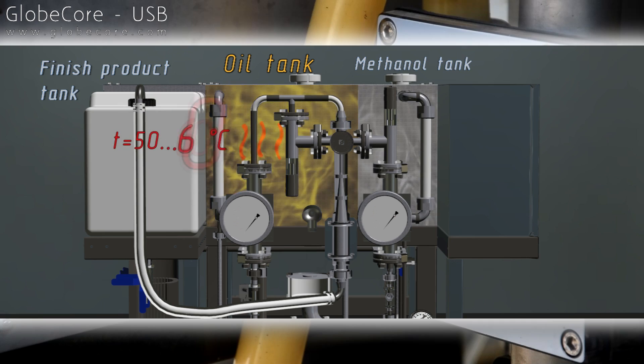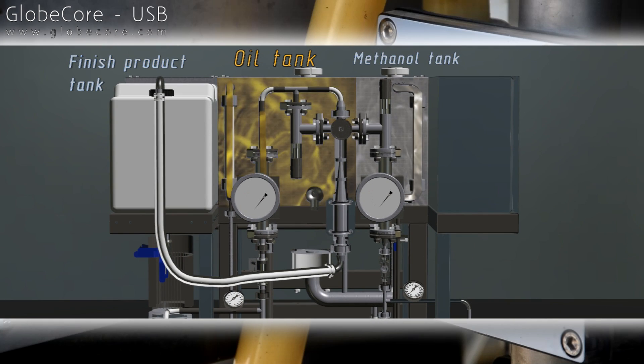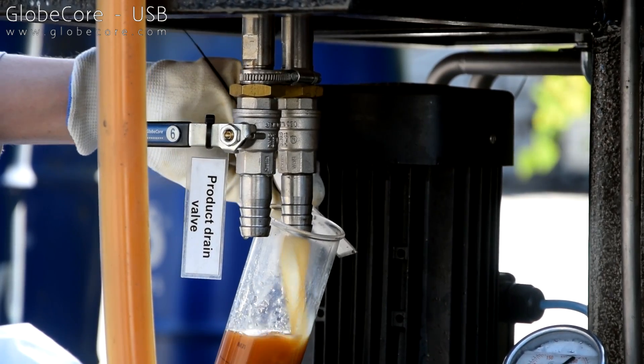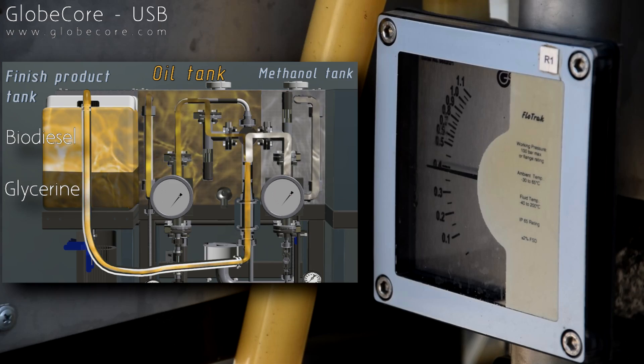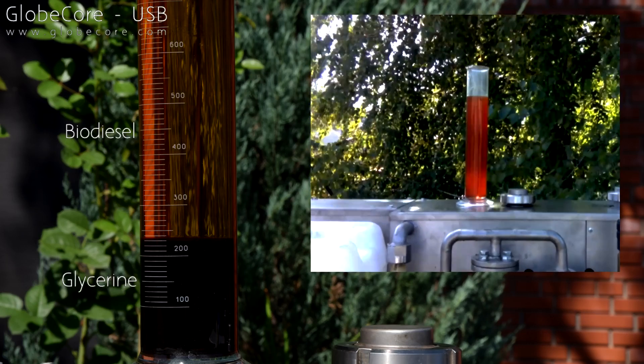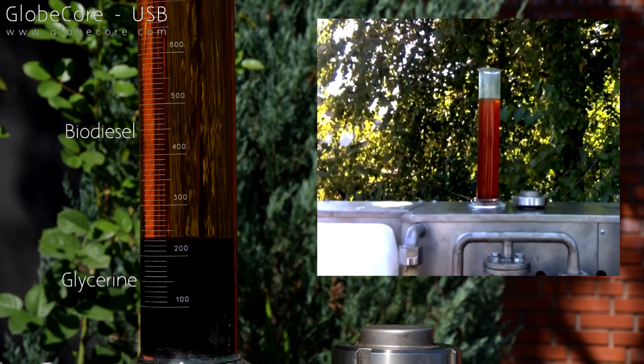The system is designed for specialized biodiesel production facilities, as well as for oil refineries, food processing facilities or farms. The operation principle, as exemplified by a demonstrator unit, is to prepare the components and create the conditions required for transesterification. One vessel is filled with vegetable oil – in our case, waste frying oil. The other vessel is filled with a solution of catalyst in methanol. Oil temperature is set to 50 degrees centigrade and oil heating is engaged. When the temperature reaches the set point, we start the oil and methanol pumps to circulate. Oil and methanol pass through the mixer and then, mixed, flow into the product vessel, where the liquid fractionates. When water and glycerin separate from biodiesel, we open the corresponding valve on the unit for product output.